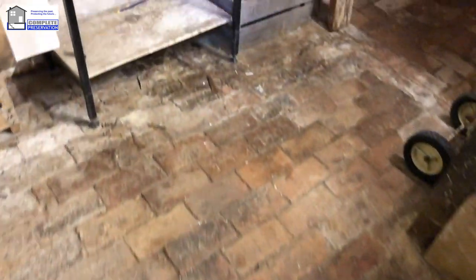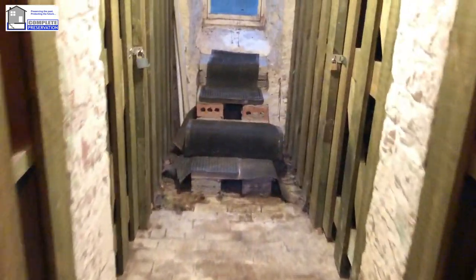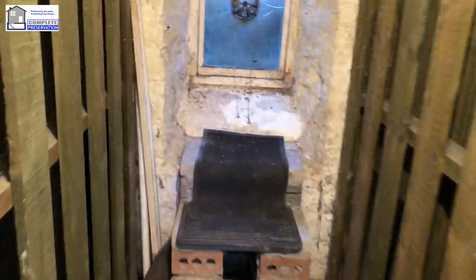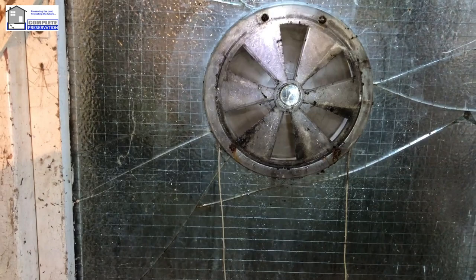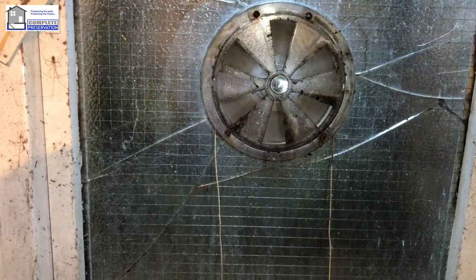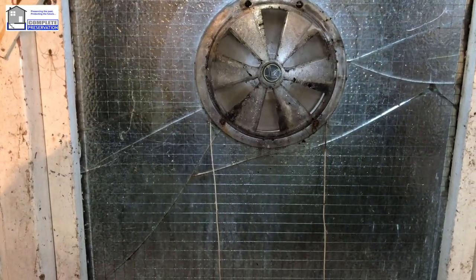Being a basement area, a lot of the moisture production comes from the flats above, so if you start measuring the vapor pressure in here it's always going to be more than outside. There's only one part in here that's got some ventilation — this one here — and it was stuck. I've just freed it up and there's actually quite a lot of air coming through now, probably about 10–12 liters per second. That is probably one of the causes.